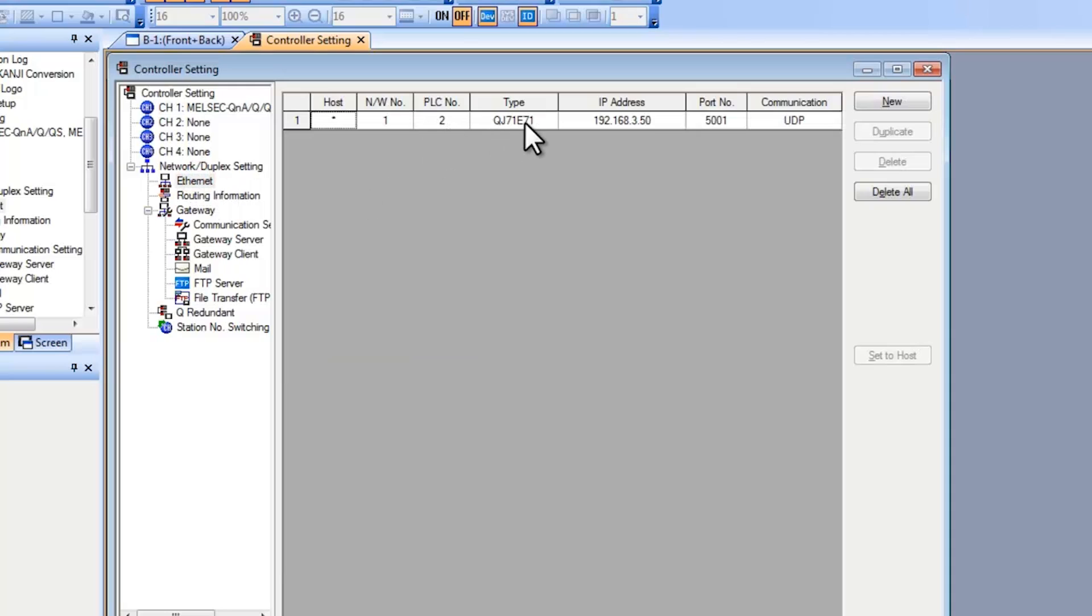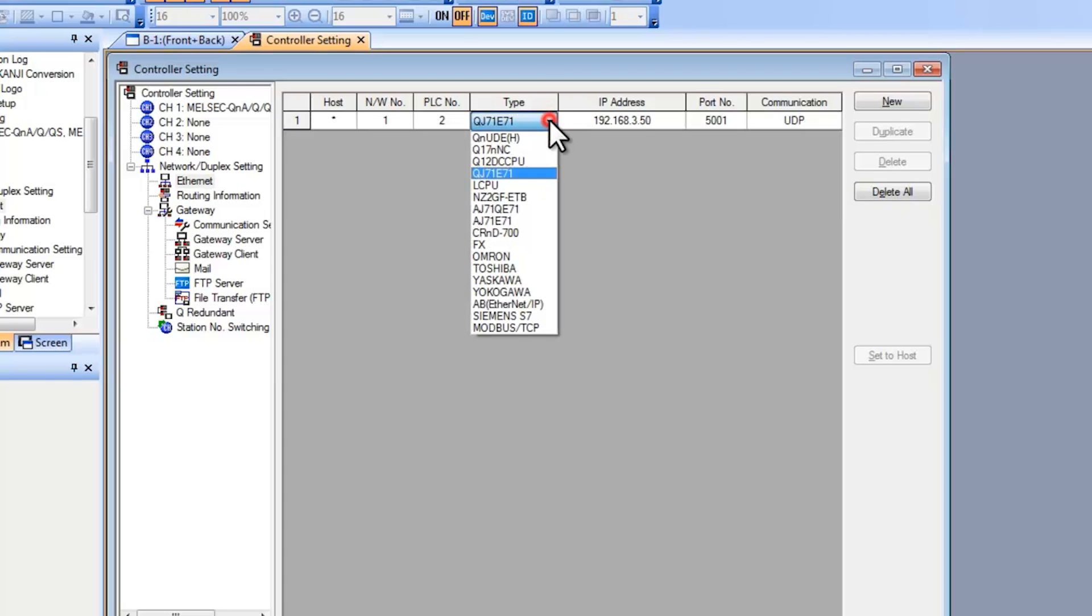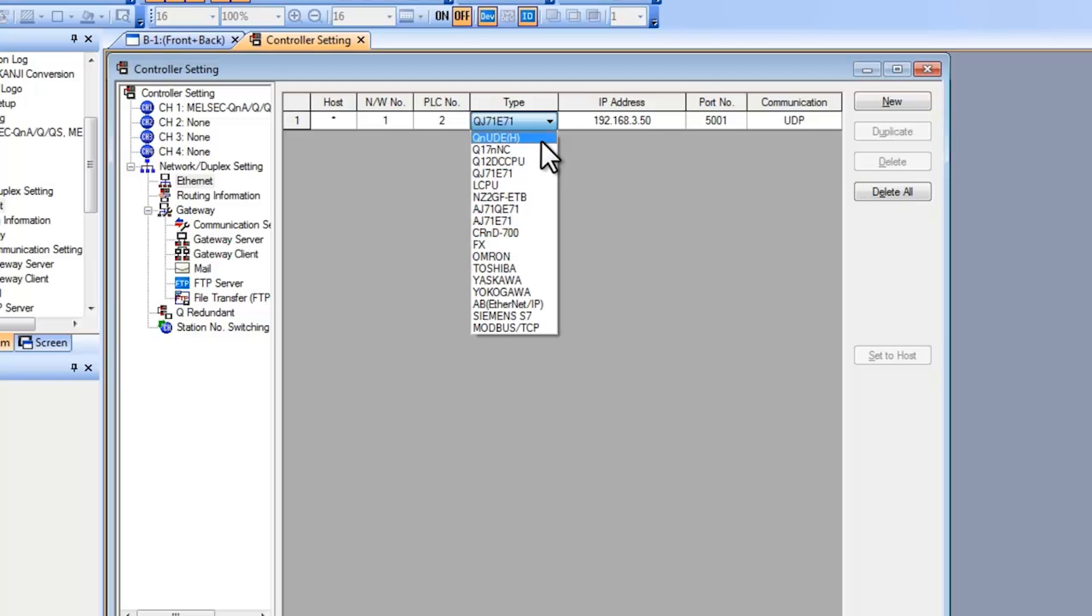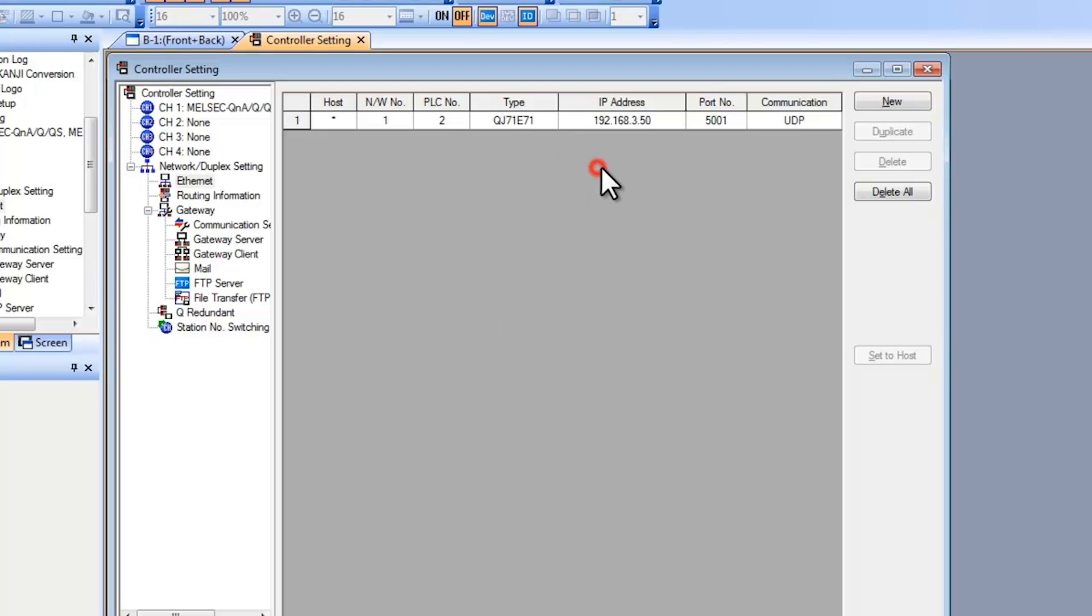Now for the type you select what you're communicating to. You have a drop down here with many options. If you're using FX select FX. If you're using a built-in Ethernet port on an IQ platform PLC, you select QNUDEH. In my case I'm using Ethernet module. Then you set your IP address. This needs to match the setting in the PLC.